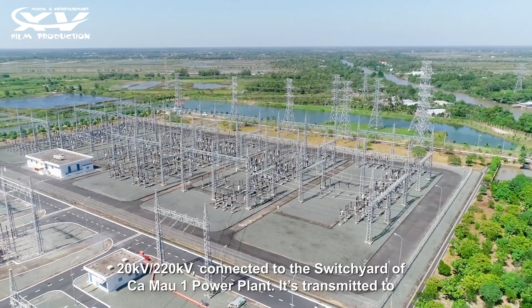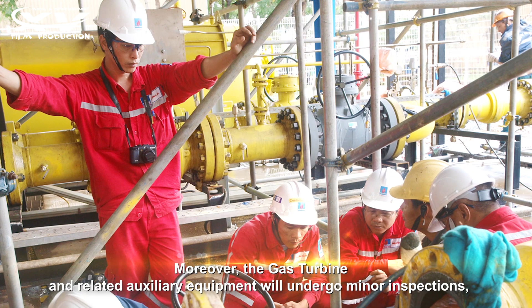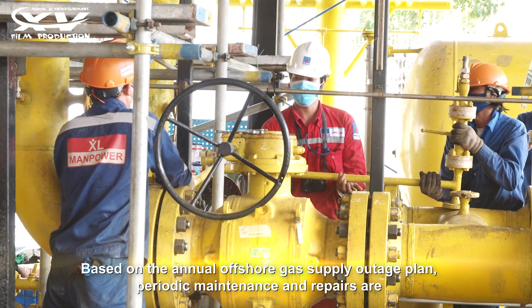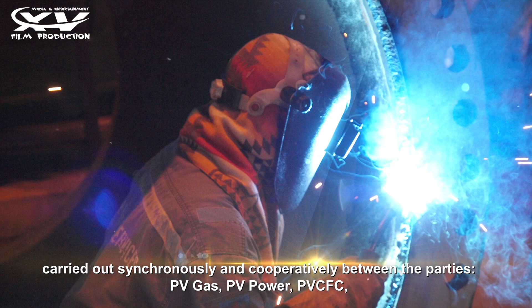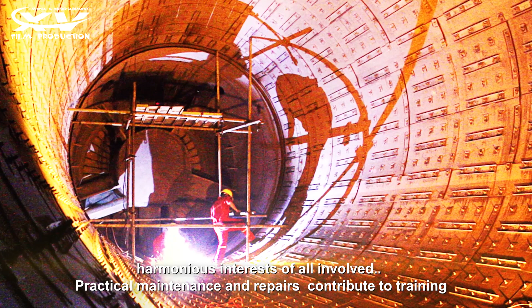To operate the two power plants safely and effectively and ensure long service life, the operation and maintenance of the plants must comply with the manufacturer's regulations. Moreover, the gas turbine and related auxiliary equipment will undergo minor inspections, hot gas path inspection, and overhauls at 8,300, 25,000, and 50,000 operating hours. Based on the annual offshore gas supply outage plan, periodic maintenance and repairs are carried out synchronously and cooperatively between the parties: PV Gas, PV Power, PVCFC, subsidiaries of EVN, Siemens, PVPS, and other relevant parties, along with ensuring the harmonious interests of all involved. Practical maintenance and repairs contribute to training the company's technical managers and engineers, as well as to accumulate more experience.